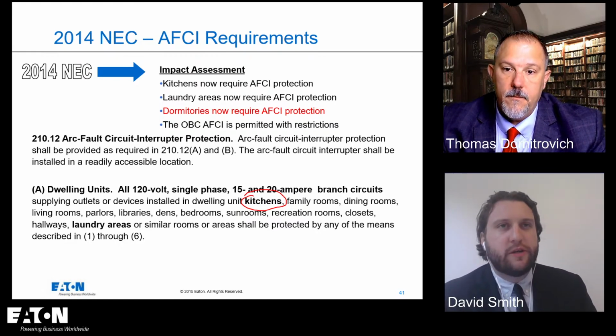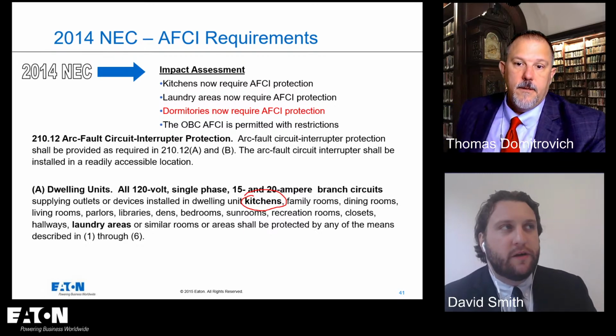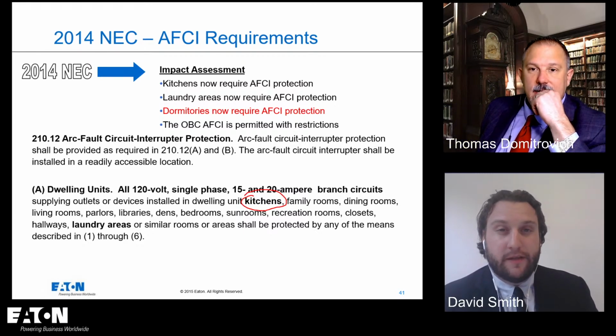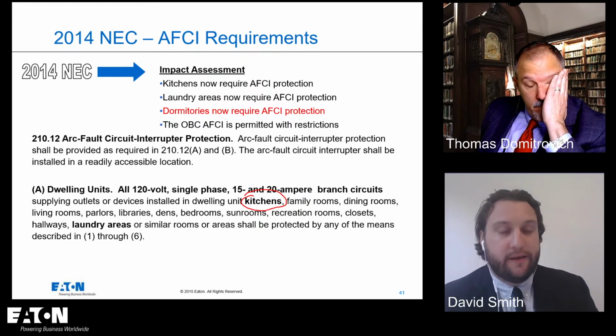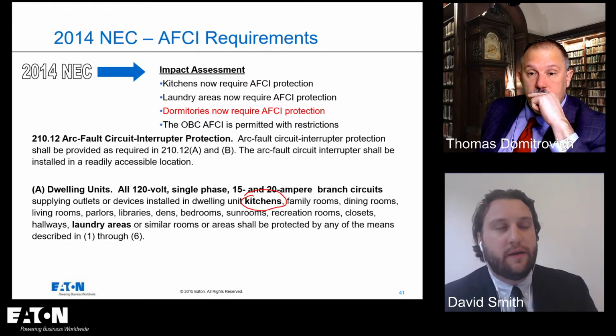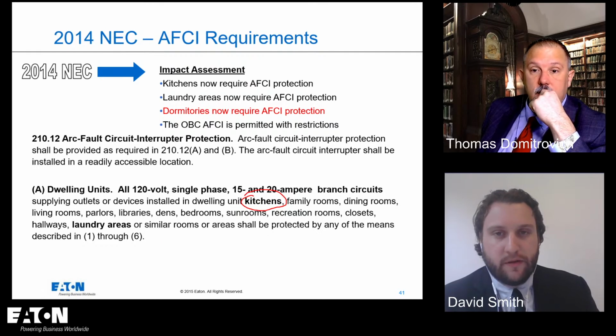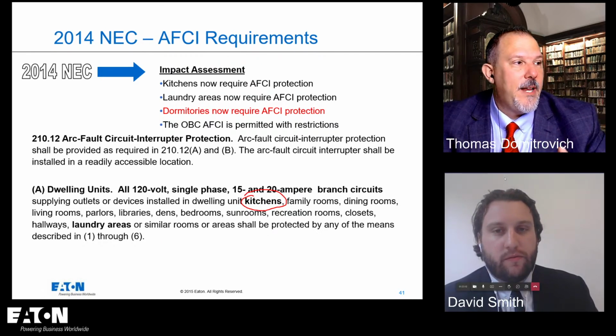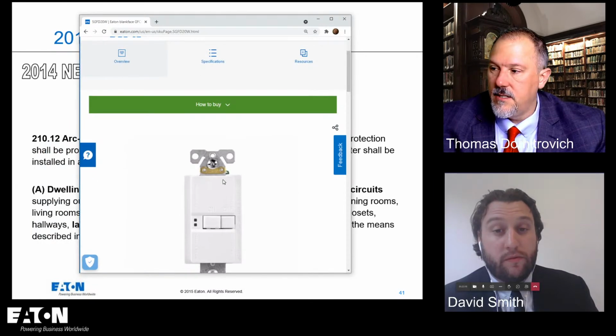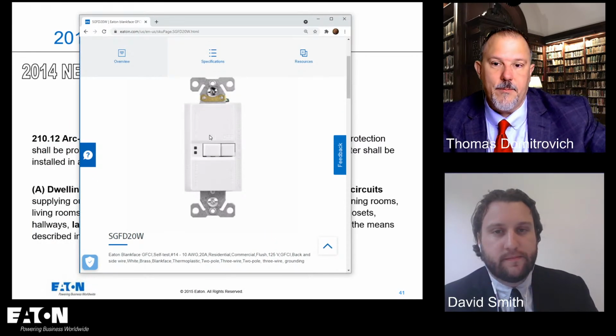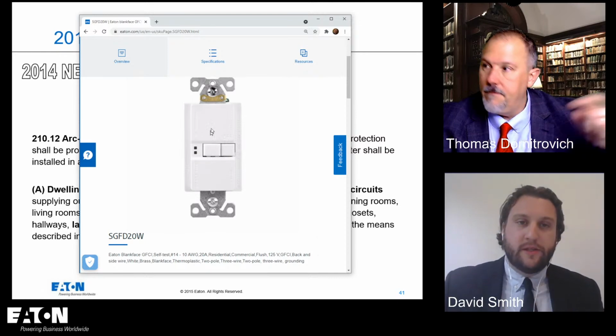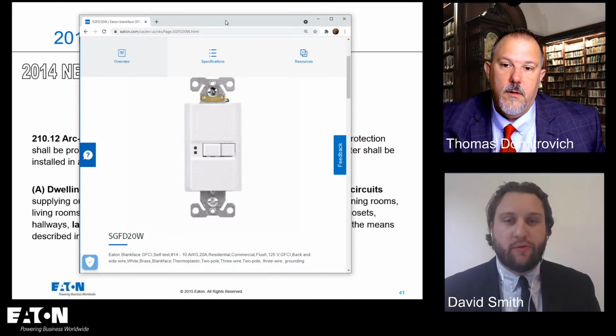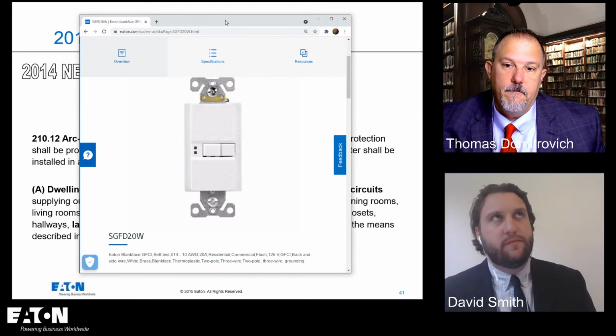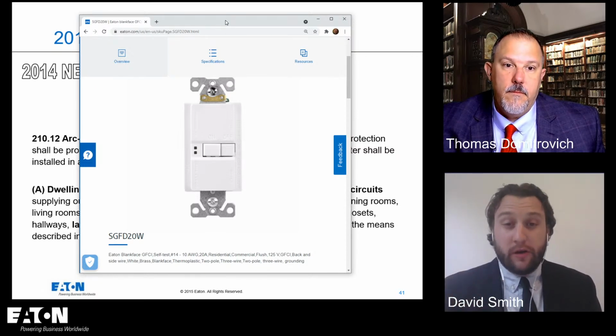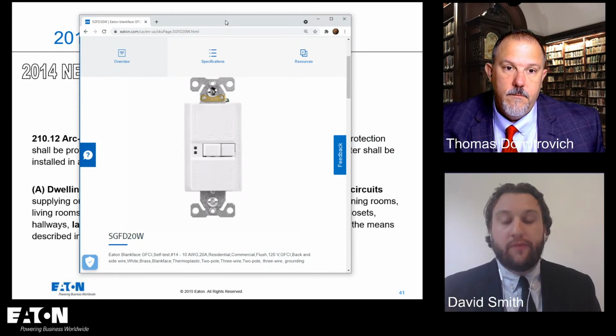Right. I just want to make sure I'm hearing you correctly on that first particular application you were talking about for the blank face GFCI. So you're saying AFCI circuit breaker and use a blank face GFCI receptacle. No. And so you would have this device. Yes. And then this would feed the receptacle. Got it. Okay. So that would be upstream from the receptacle that's actually going for the refrigerator. And if you're going to go with that, that would be at a readily accessible location. That's exactly right. Yes.